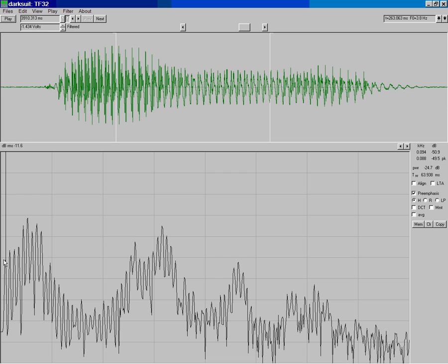If you see a harmonic that you may want to measure the peak of, you click to the left of that harmonic or to the right and simply drag the cursor across that peak. And what it does is that it takes that window that you've passed the cursor through, and the computer automatically looks for the true maximum value there in terms of the magnitude of that and then also what frequency it's at.